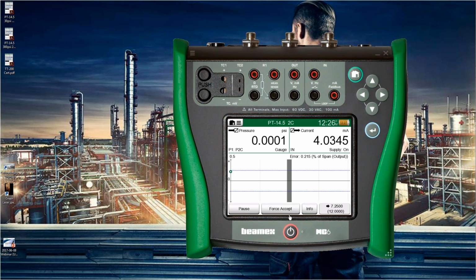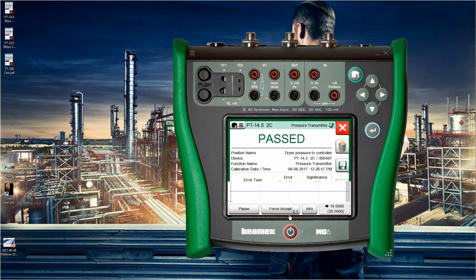I have a 2-second delay in between each test point, so let me just close off my vent and I'll take it up. I don't need to get it exactly on 17.25. I'll just stop it in that gray bar, and it's calculating the output versus the input, so I don't have to get it exact. I just need to get it close. And it's calculating the error across the top. So we'll get an error statement here, and I'm doing this real quick on purpose. So my maximum error was 0.215% of span.